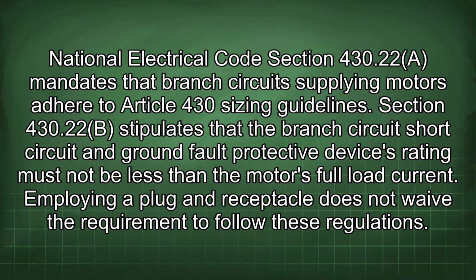National Electrical Code Section 430.22 mandates that branch circuits supplying motors adhere to Article 430 sizing guidelines. Section 430.22(b) stipulates that the branch circuit, short circuit, and ground fault protective device's rating must not be less than the motor's full load current. Employing a plug and receptacle does not waive the requirement to follow these regulations.